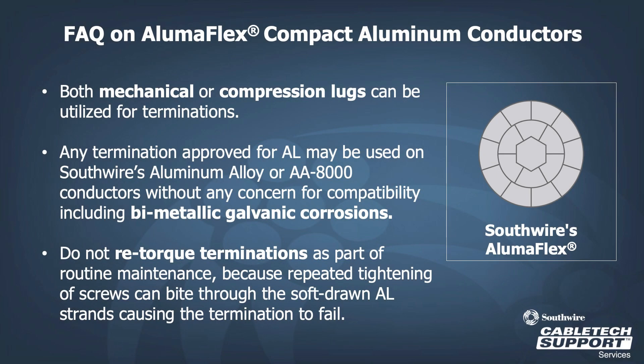Here is a good time to address some frequently asked questions about compact aluminum conductors. When asked about terminations, both mechanical and compression lugs can be utilized. Any termination approved for aluminum conductors may be used on AlumaFlex conductors without any concern for compatibility, including bimetallic galvanic corrosion. Do not re-torque the terminations as part of your routine maintenance, as repeated tightening of screws can bite through the soft drawn aluminum strands, causing the terminations to fail.